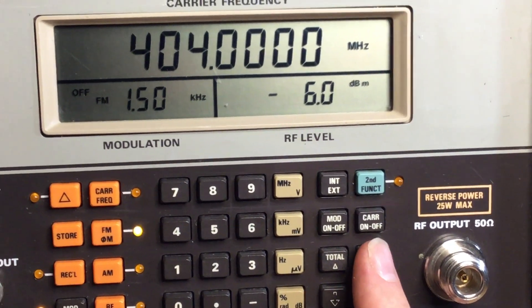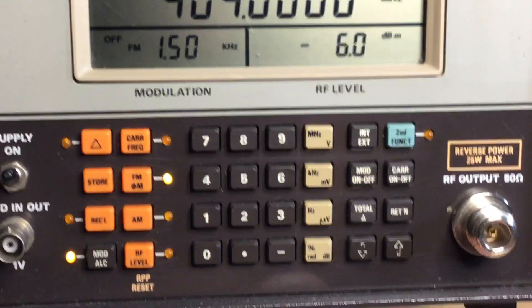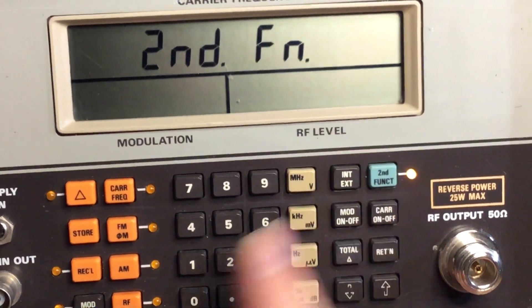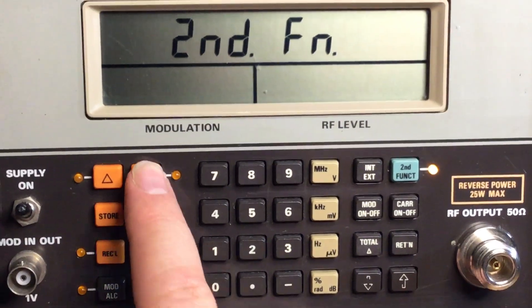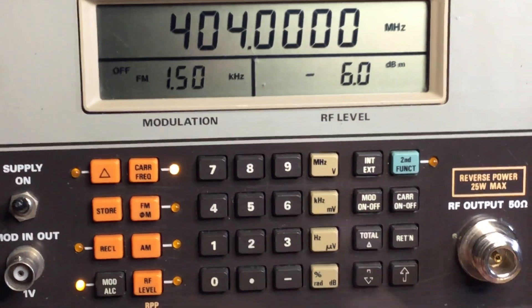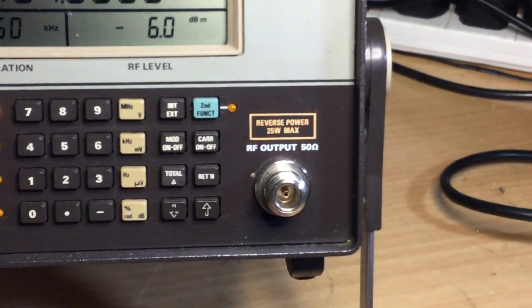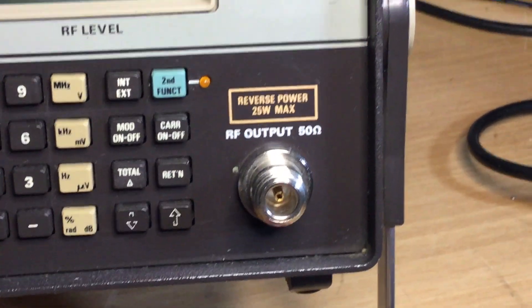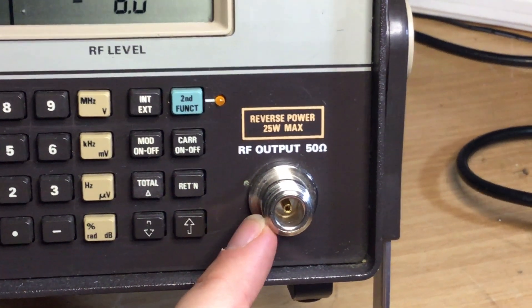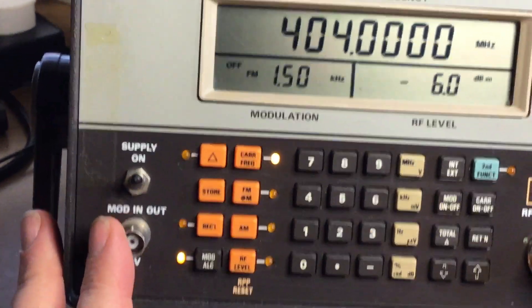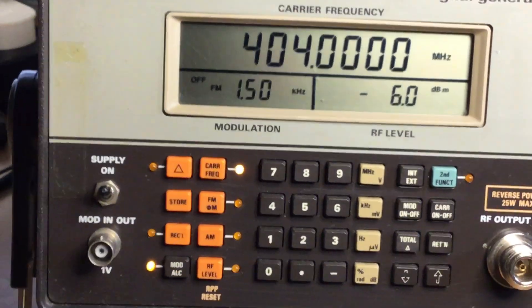There's quite a few functions on it. There's even more functions with the second function key there, where you can press to get second functions, so there's more to it as well that you can set up, which is in the manual for the test set. Again, an N-type 50 ohm output. You can give reverse power of 25 watts if you were to accidentally transmit back into the instrument. And then of course we've got the power supply switch here as well.